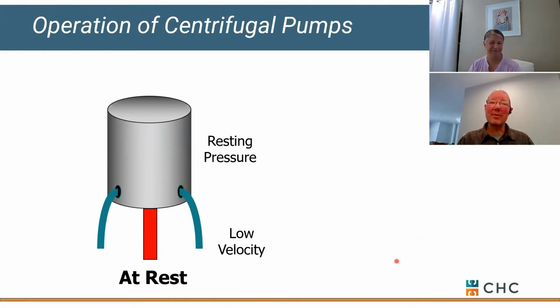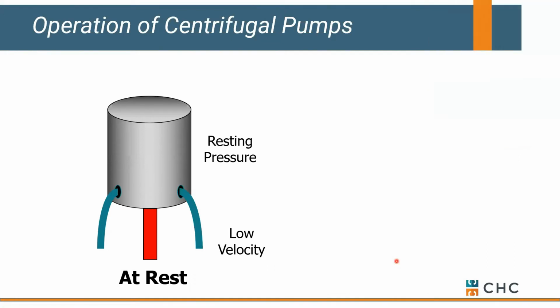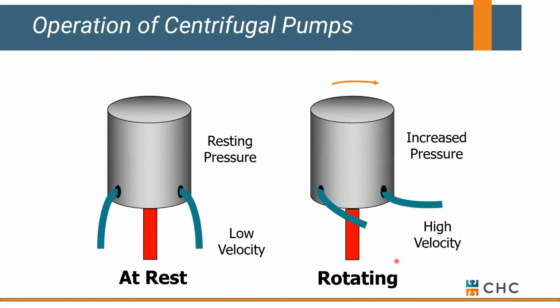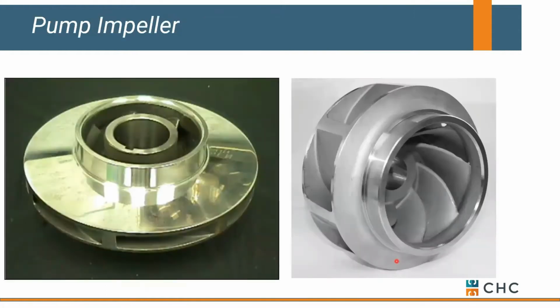If you remember, if you attended our centrifugal pump class, coffee can with holes in it and water just flows out. And if we want to develop some pressure in that pump, or we want to be able to spray water out of those holes a little farther or faster, then we start to rotate that can. Okay, and as we rotate that can, we develop some velocity, and now we can send water out to our system. And we do that with our coffee can as our impeller. Okay, and all we're doing with that impeller is handling water that's flowing in. We're guiding it with our vanes and ultimately flipping it towards the discharge.